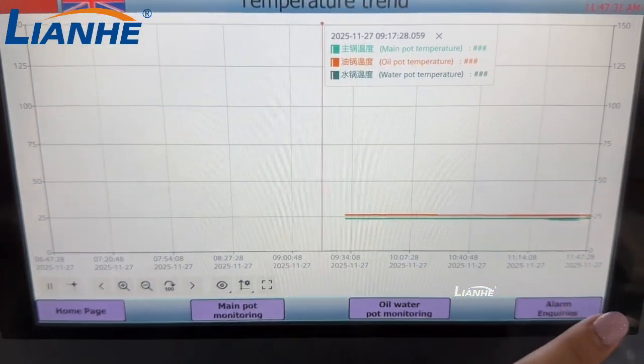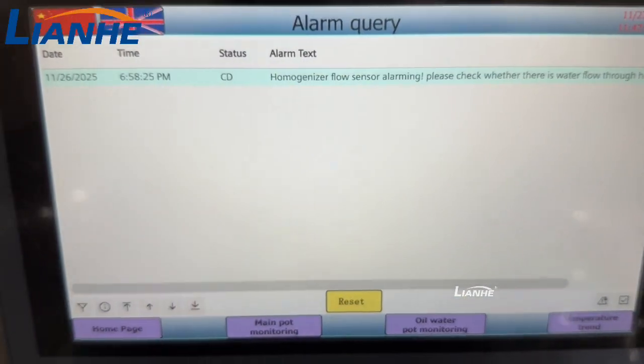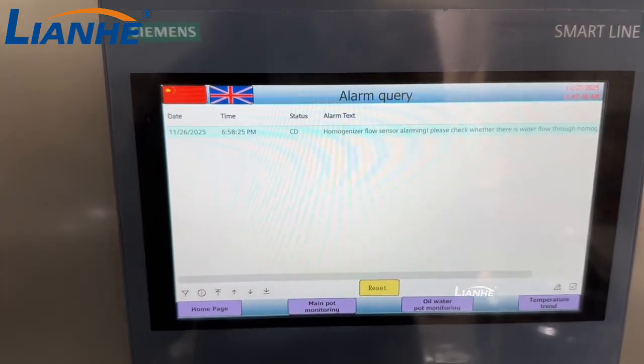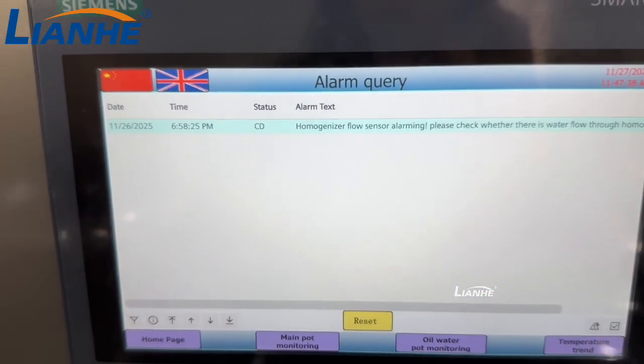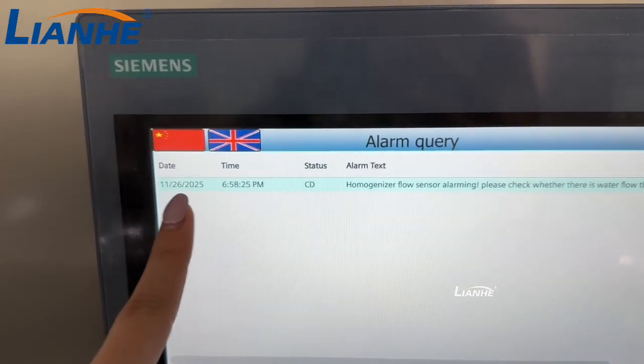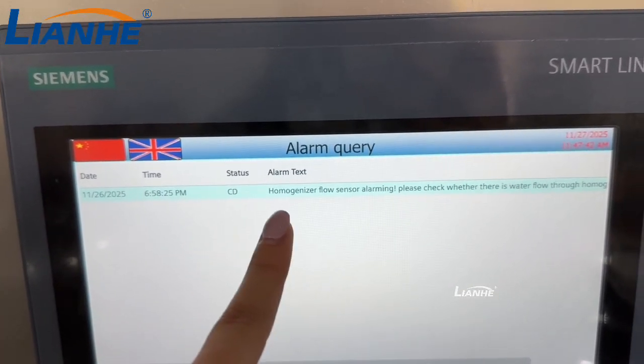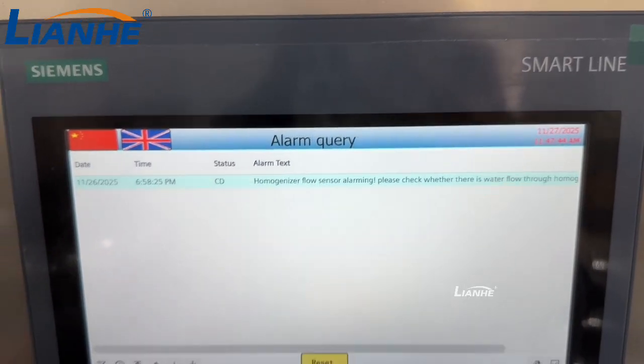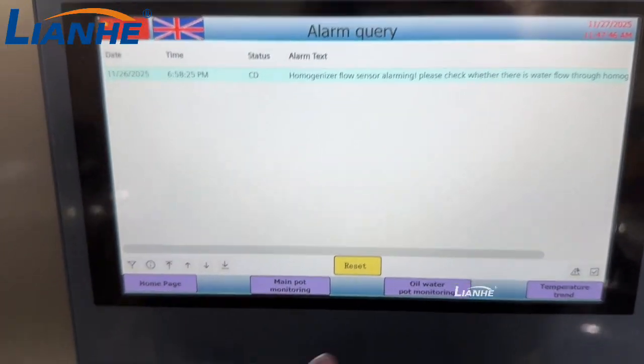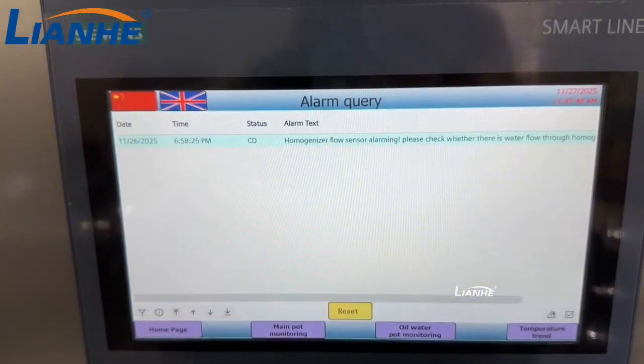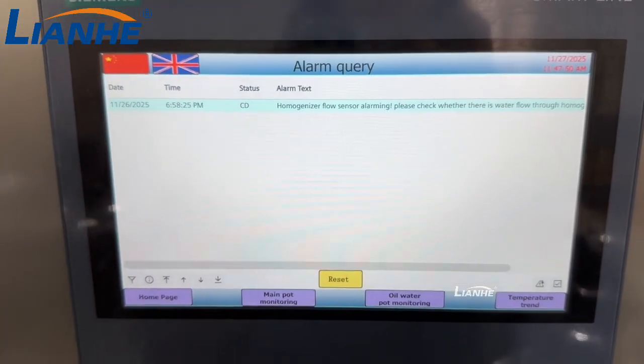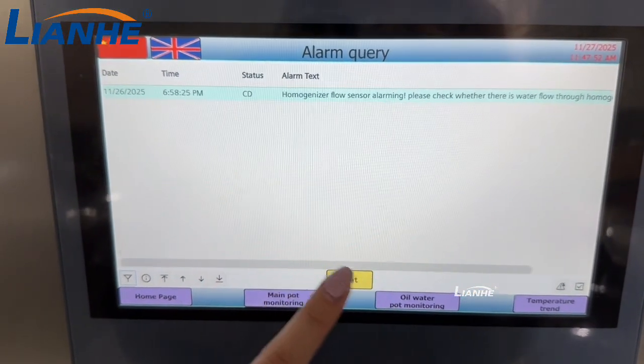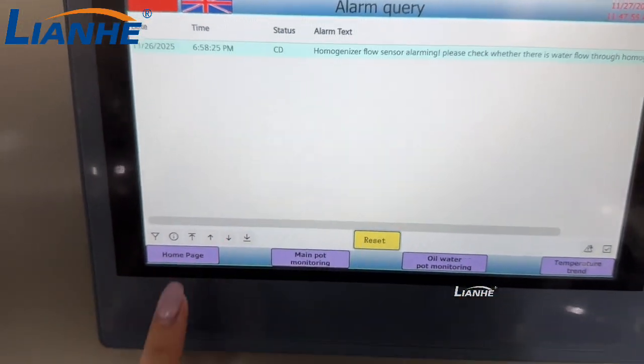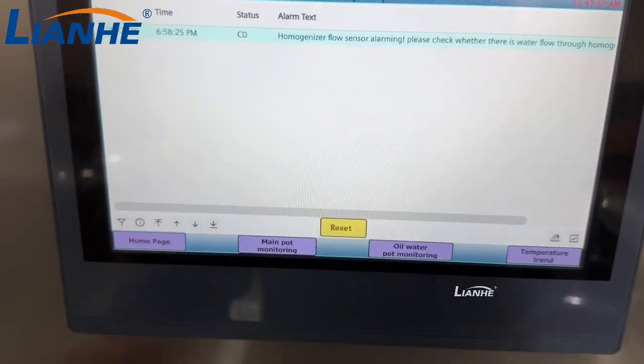And then you may check the alarm inquiries. This alarm inquiry will tell you what is wrong with this machine. You can check here the date, time, status, and the alarm text will tell you what is going wrong with this machine. And if you fix the bug of this machine, you can push this reset button. And then let's go back to the home page.